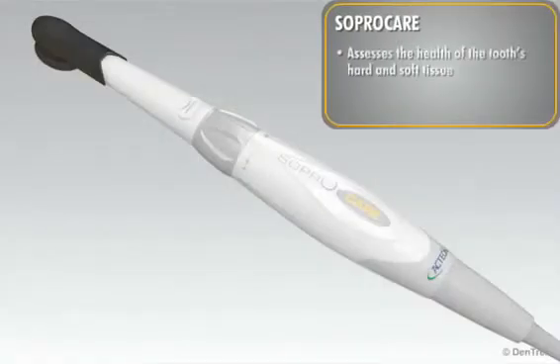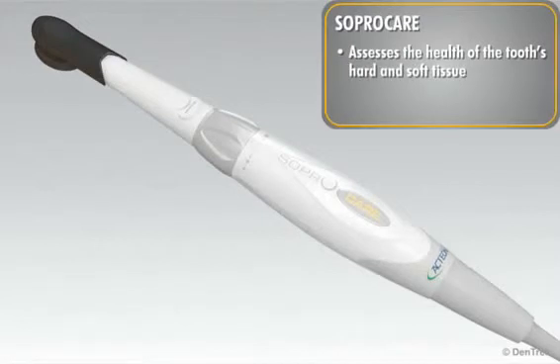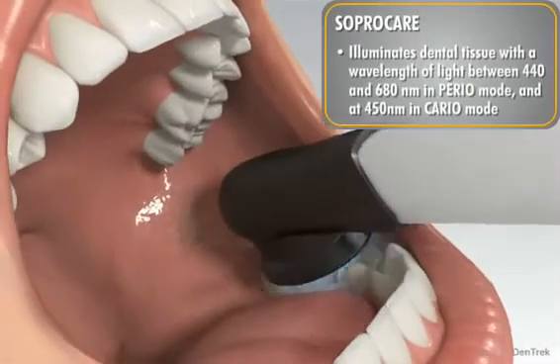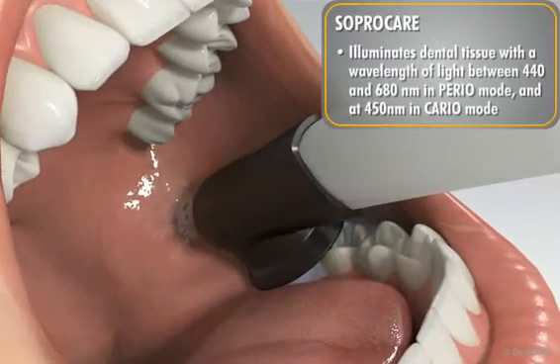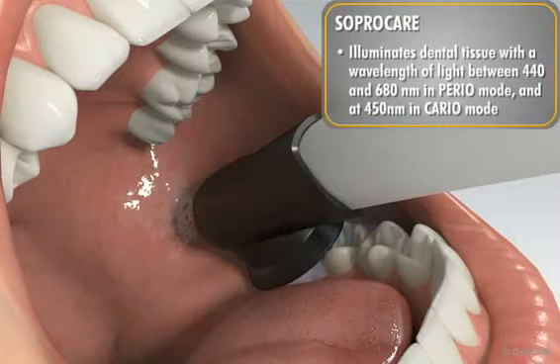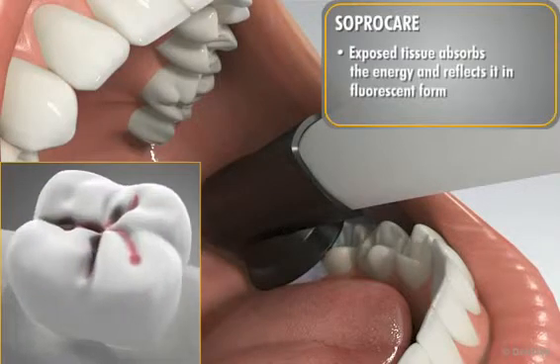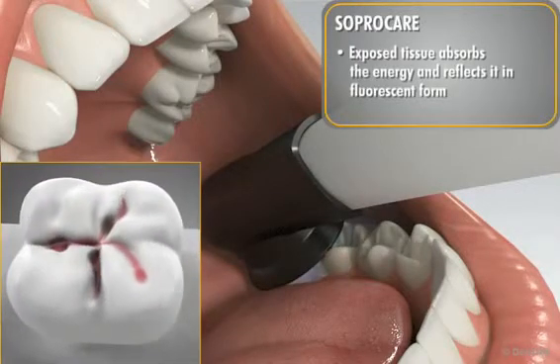SoproCare assesses the health of the tooth's hard tissue as well as the soft tissue that surrounds it. It illuminates dental tissue with a specific wavelength of light — between 440 and 680 nanometers in perio mode and at 450 nanometers in cario mode. The exposed tissue absorbs the energy and reflects it in fluorescent form.